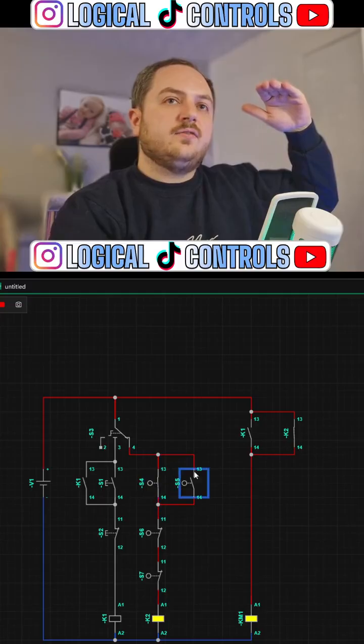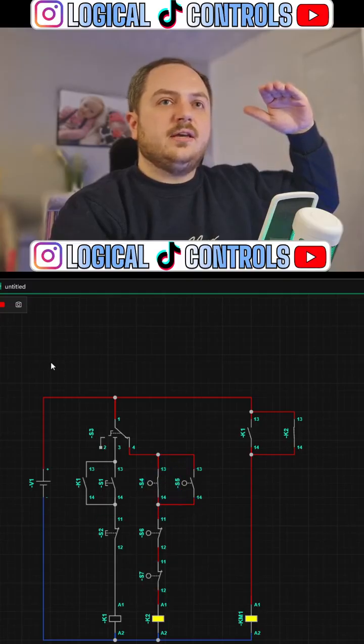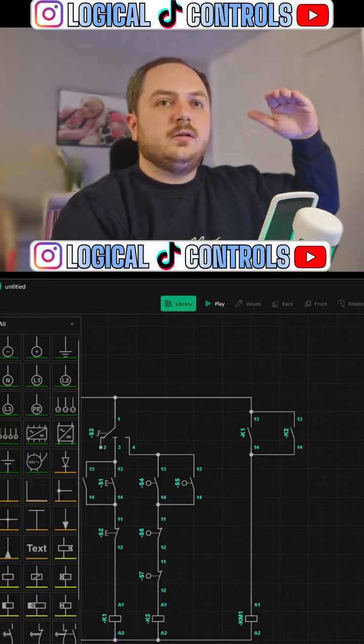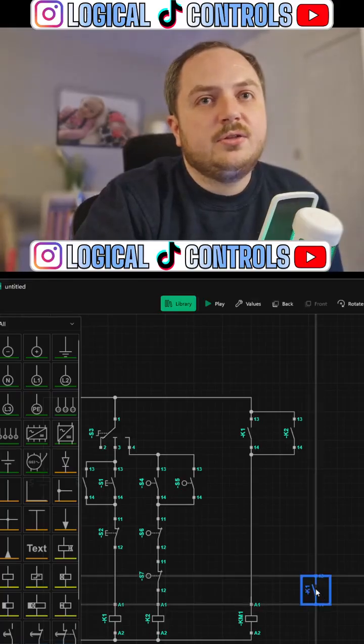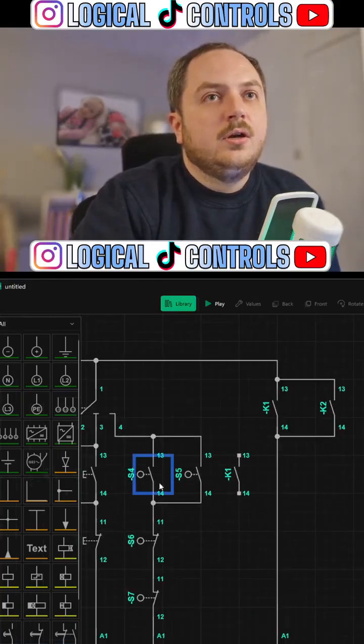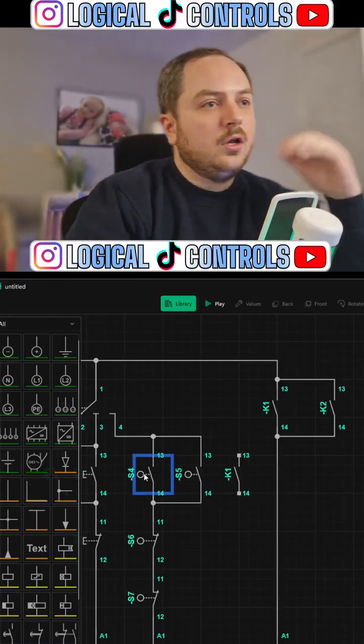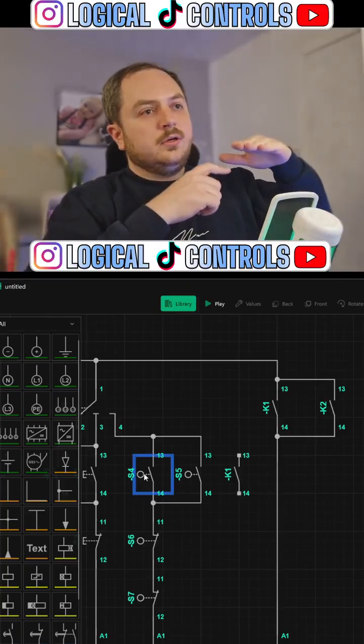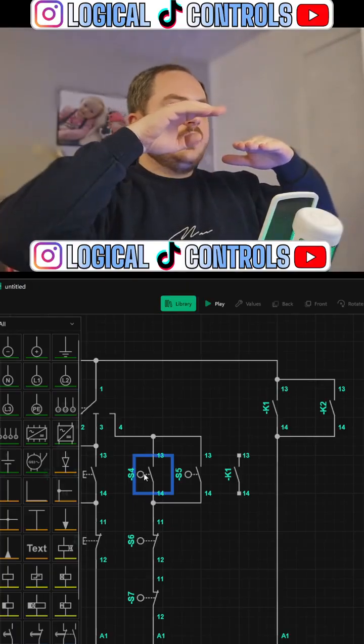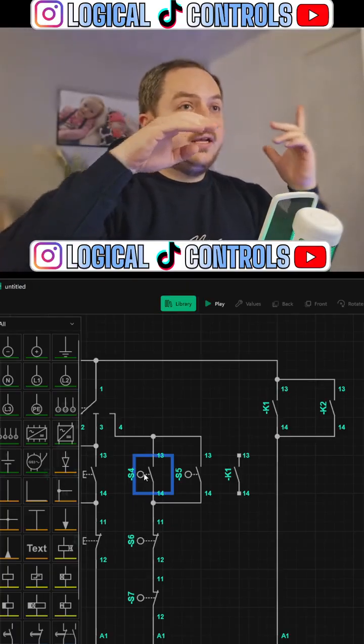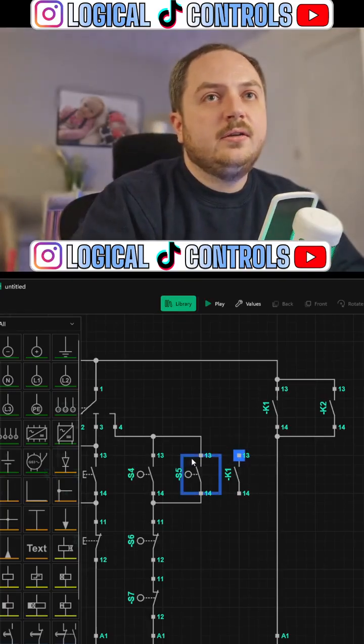Actually, I should have a latch in there for S4, so let me put a latch in and make it right, because the minute S4 closes and the pump comes on, the level starts to rise again and S4 would open. So you have to latch it in, I'd missed that out. Let me just do that and tidy it up a little.